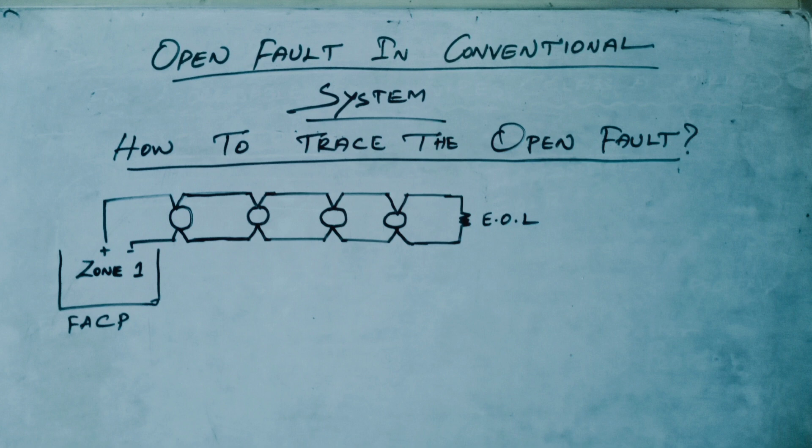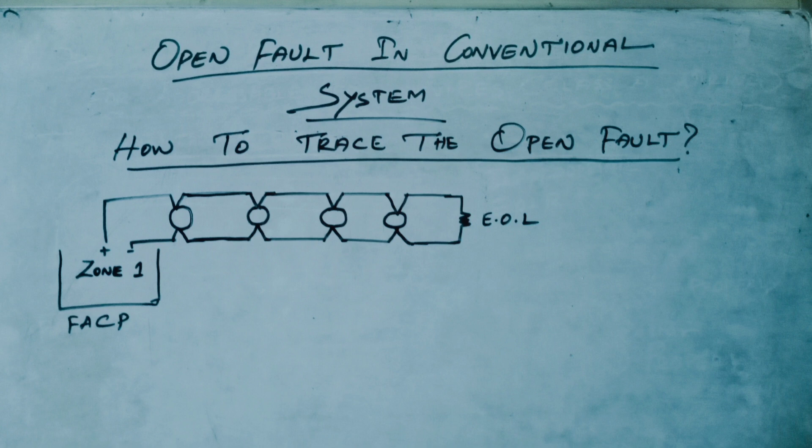It is very hard to find out where the open trouble is occurring when you have many devices installed in many rooms. In a conventional system, I recommend cutting off continuity and checking in the middle of the zone. Sometimes, if you are lucky, you can find the open fault at the very first device of the zone.